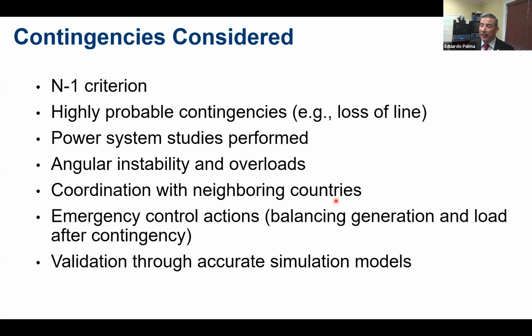There is a big concern or a big risk that neighboring countries would be affected, and there needs to be coordination between countries, between contracts that happen with the transmission lines between countries. So the emergency control actions basically are there to balance generation and load after these contingencies, the ones mentioned above. The validation through an accurate simulation model was a must. Not only a must because if you do not validate it before you install it, what you get is a system that once it is installed does perform some actions, but they could be fine-tuned after the installation date.